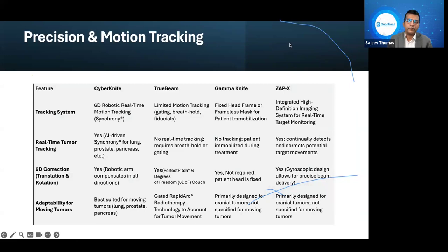If you look into the precision, we could see the CyberKnife system uses robotic real-time motion tracking, that is Synchrony. TrueBeam now is using an identify system with Varian, or it can be coupled with other providers, while Gamma Knife is using a fixed head or frameless mask for patient immobilization. ZAP-X is using an integrated high-definition imaging system for real-time target monitoring. So here, another tumor tracking method is available for TrueBeam. It is not real-time tracking, but it is available with the new models. Here also, it is available with the new models, and ZAP-X continuously detects as well. And for 6D correction, yes, the robotic arm compensates for the 6D correction. And TrueBeam, it is compensated.